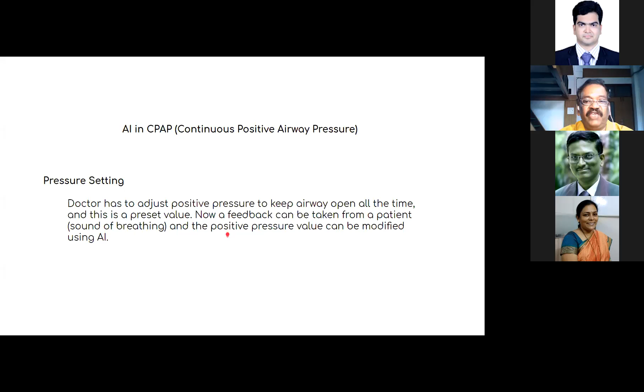So we can now take feedback from the patient, for example the sound of breathing. If the patient starts snoring, the machine can increase its pressure limit till the snoring stops. So it is not a preset value. It can be dependent on the patient's requirement. Even when the patient is sleeping on his side, an accelerometer sensor can be used to detect the position of the patient and adjust the positive pressure accordingly. So instead of giving a constant positive pressure, the machine can be made more intelligent by changing the pressure as per the patient's requirement. And the last thing we will discuss is the oxygen concentration.